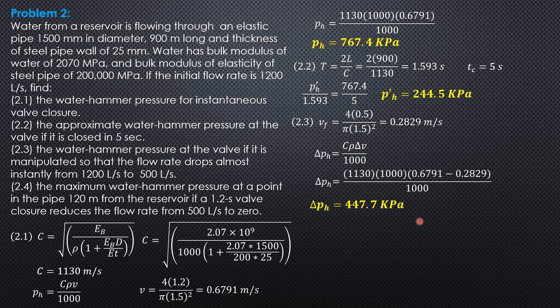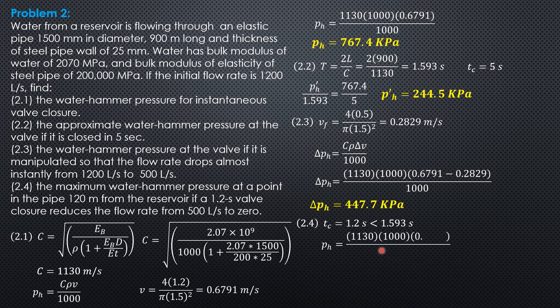For Part D, find the maximum water hammer pressure at a point 120 meters from the reservoir, given a 1.2-second valve closure reducing flow from 500 L/s to zero. First solve for pH: actual closure time 1.2 seconds is less than 1.593 seconds, so this is sudden closure. For sudden closure, pH = C × ρ × V / 1,000. Velocity is 0.2829 m/s when discharge is 500 liters per second, and final velocity is zero. So pH = 319.7 kilopascals.